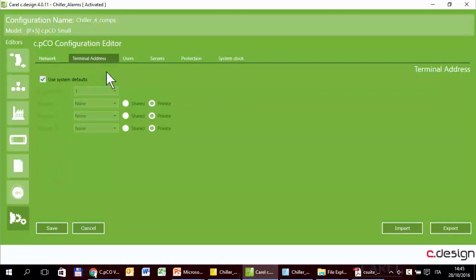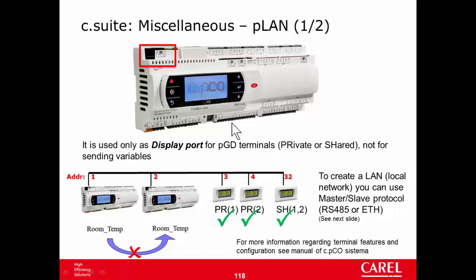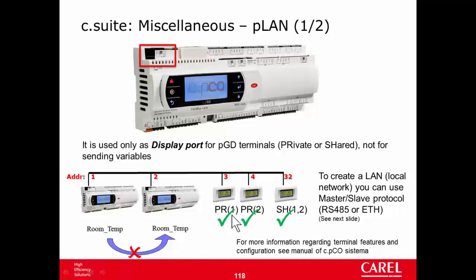Terminal address regards the configuration of the PGD1 external terminals. Each c.pCO can show its mask into up to three external terminals. The controller has an address in this network that is called PLAN. In this case, there are two CPCO, address one and two, and then three terminals. The terminals can be configured as private or shared, private for a specific device or shared by two or more.